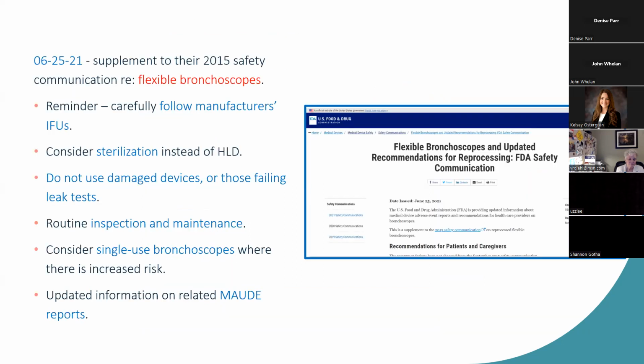June of 2021, the FDA provided notice related to bronchoscopes. They reinforced following the manufacturer's IFUs to consider sterilization instead of high-level disinfection when feasible, and not to use damaged devices or bronchoscopes that have failed a leak test. That second part, doesn't it seem like somebody should not have to say that? But when you think of the reality of many endoscopy facilities and clinics, they just have enough inventory, no cushion of extra. So they may use things beyond points where they should.